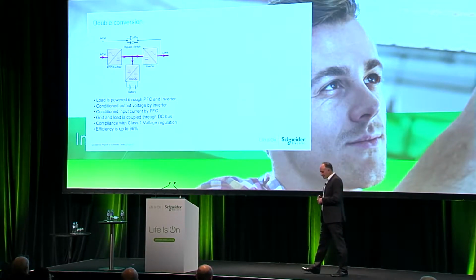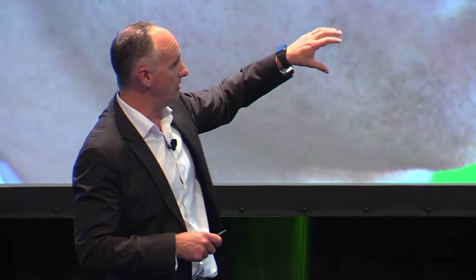And this will be a little bit technical, but I can see I've got quite a mixed audience here, so I'll try and get it in the middle. In order to understand how e-conversion works, let's recap how a double conversion UPS works. In essence, you have a rectifier, an inverter, and these days a DC to DC converter sitting at the bottom, charging and taking bidirectional flow in and out of the battery. In normal operation, power flows in through the rectifier onto the DC bus, charges the battery, and goes out through the inverter. If there's a mains failure, we fail over and draw power out of the battery. That's how the double conversion UPS has worked for a long time.